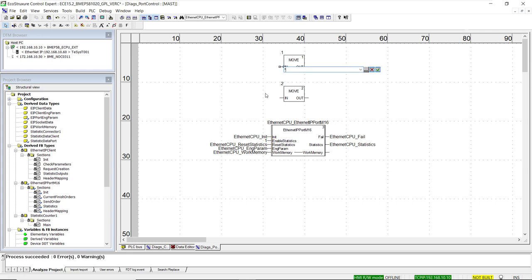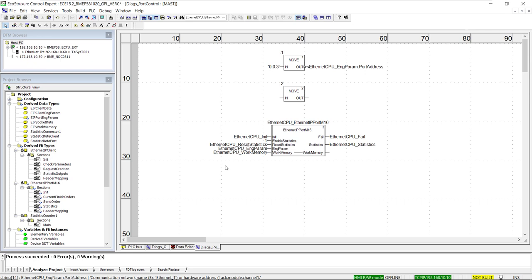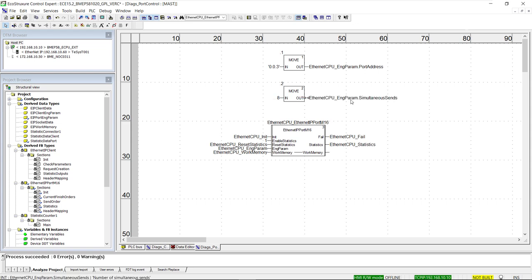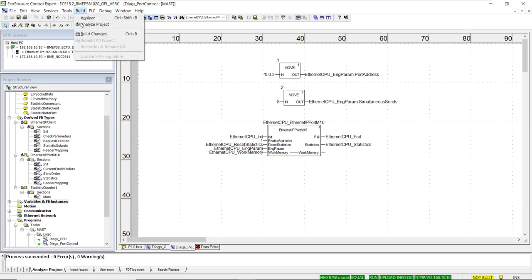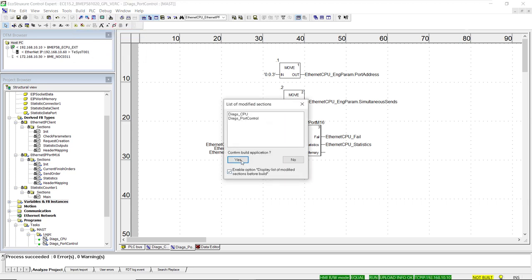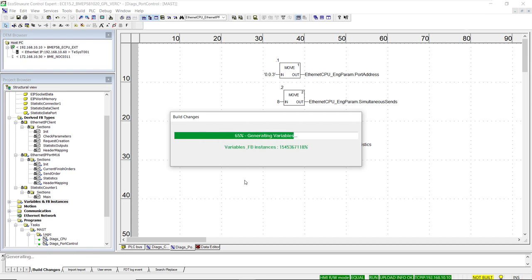For the address, we use 0.0.3 for the Ethernet port embedded in the CPU. For simultaneous messages, a value of 8 is transferred, although the function block capacity is 16. If a timeout value of 0 is entered, the function block defaults to a timeout of 3 seconds. We then proceed to build the changes in the application and, since we are connected online with the controller, the program is transferred to the PLC at the same time.